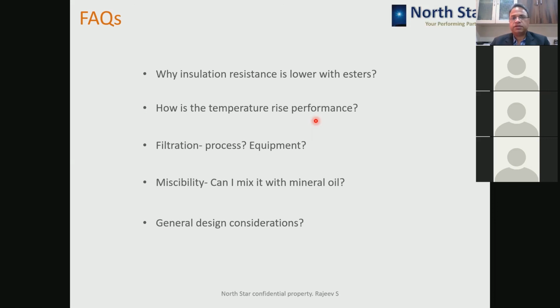Okay. Filtration process equipment: yes, normally you can use a normal filtration machine, but since it is viscous, the floating particles can cause a drop in BDV. So you need to have finer filters compared to a mineral oil filtration plant. And since it is viscous, the capacity of the pump is supposed to be higher compared to mineral oil. Miscibility: can I mix it with mineral oil? Yes, they are 100% miscible.